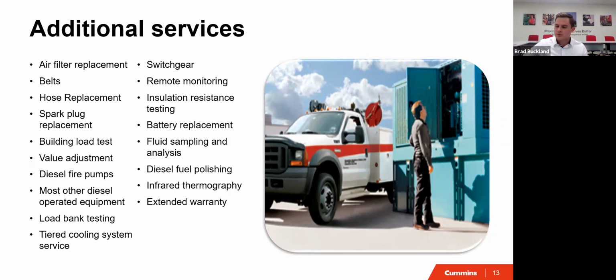Everything about planned maintenance is about making sure that when your generator isn't in use, it's out of sight, out of mind—you're not thinking about it—but when the snowpocalypse happens, you can trust it's ready to go. That's where additional services like fluid sampling and the building load test come in. A building load test is a common industry term meaning we put the generator onto the building power, turning it on as if power is lost, and manually switching over to your building's load, based on the requirement of your building at that time.